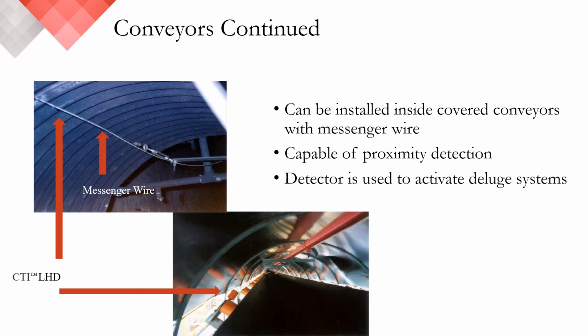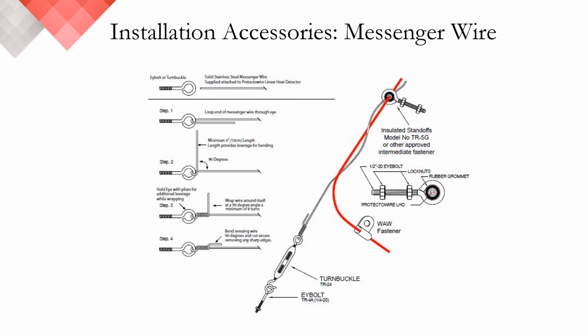In some cases, the conveyors are covered with a metal hood. In these areas, we can provide detection not only below in the area of the bearings and belts, but also above in the area where the material is being moved. In these areas, however, access to connection points to support the linear heat are limited. To accommodate long spans like this, you have the option of having the linear heat detector coupled with a messenger wire. Installing the messenger detector requires anchor bolts and turnbuckles to maintain the tension of the support cable and eye bolts to provide additional stability. As opposed to supporting the detector every 5 feet, you can now spread these supports every 25 feet. Instructions on the proper equipment and installation are readily available.